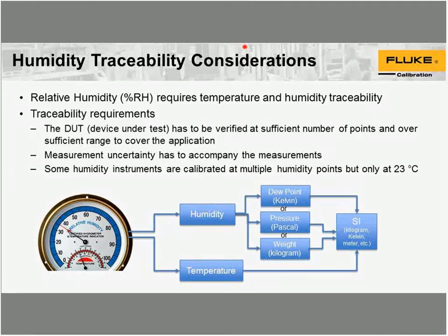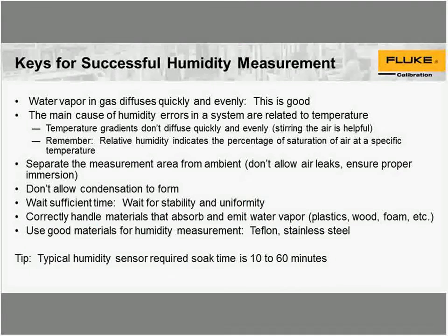So, keys for successful humidity measurement. This may be one of the most important slides in the presentation, in my opinion. These are some lessons that we've learned as we've been measuring humidity. First of all, the interesting thing about measuring humidity, and this is very useful: if this was not the case, it would make things even more challenging. But fortunately, water vapor, when it's in a gas, will diffuse very quickly and evenly.